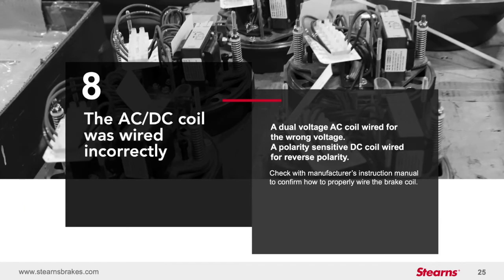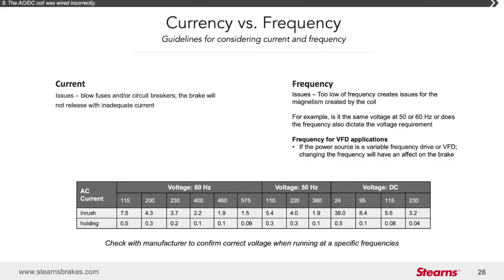Mistake number 8. The AC or DC coil was wired incorrectly. AC brakes have dual voltage coils and/or dual frequency coils, so be certain to wire the coil correctly per the manufacturer's instructions. And with DC coils, check to determine if the coil is polarity sensitive and assure that it's wired correctly. The table below shows an example of inrush and holding currents for various voltages. Inrush is typically the current needed to overcome the spring pressure that sets the brake and to overcome the brake air gap. So it takes more current at inrush to release the brake than simply to hold it released once it has been released.